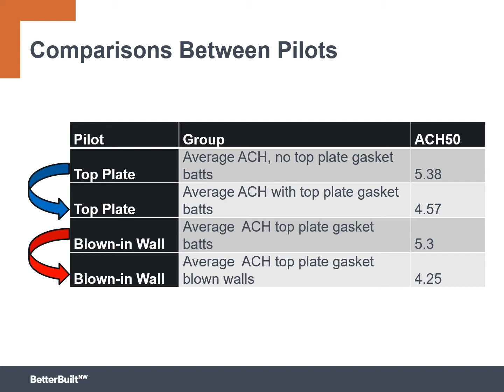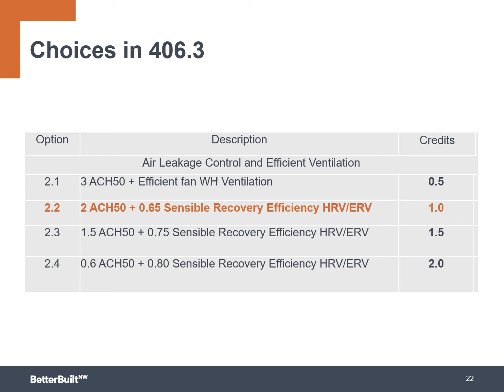Now, what if you either want or need more credits out of this section? You could go to option 2.2, where now we're getting down to 2 air changes per hour, and we're putting in at least a minimum efficiency heat recovery or energy recovery ventilator. Don't worry, we'll go much more into HRVs and ERVs a little bit later in this presentation and an entire other presentation just focused on them. So let's take a look at ways that we might get down to 2 air changes per hour.